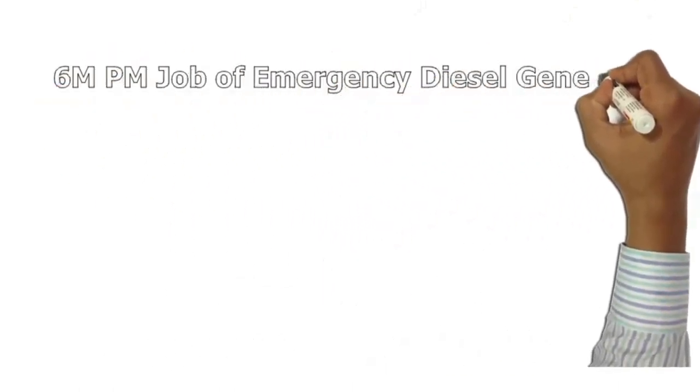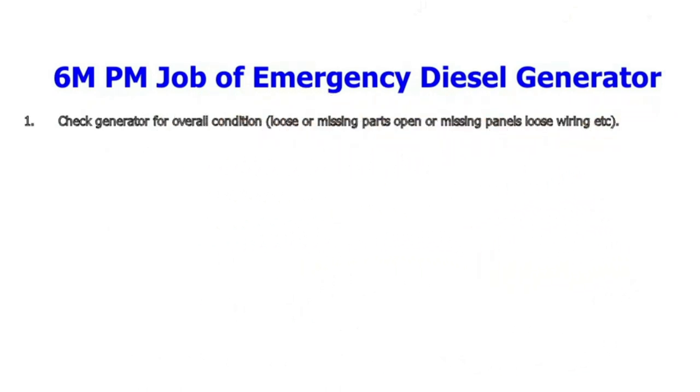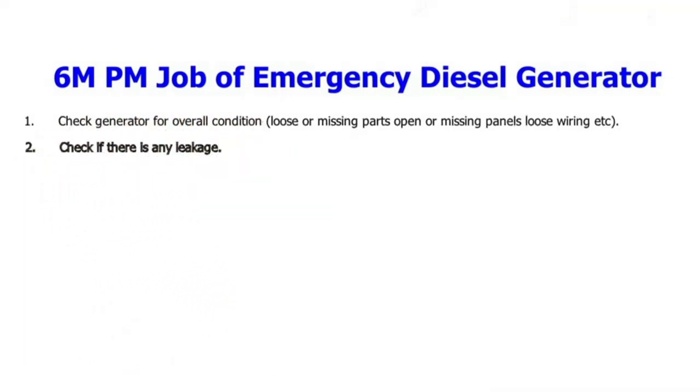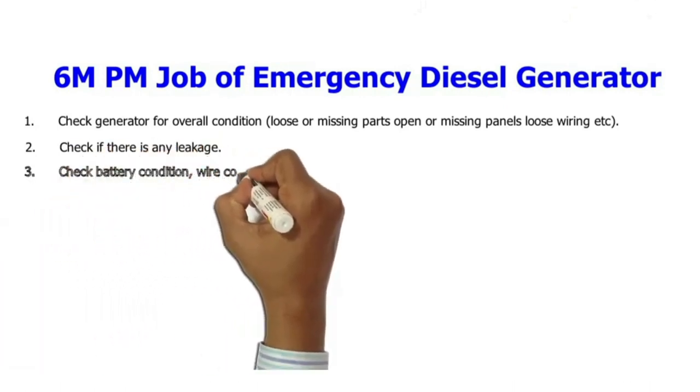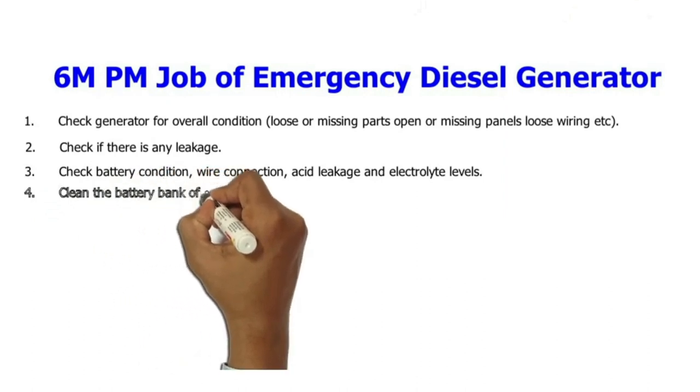6M PM job of emergency diesel generator: 1. Check generator for overall condition — loose or missing parts, open or missing panels, loose wiring, etc. 2. Check if there is any leakage. 3. Check battery condition, wire connection, acid leakage and electrolyte levels.